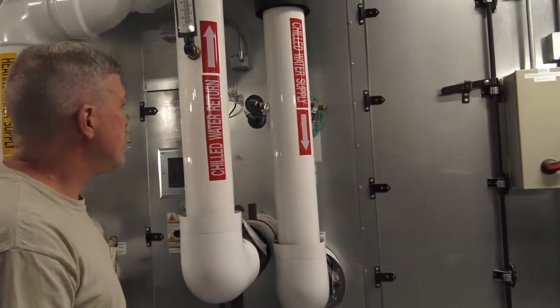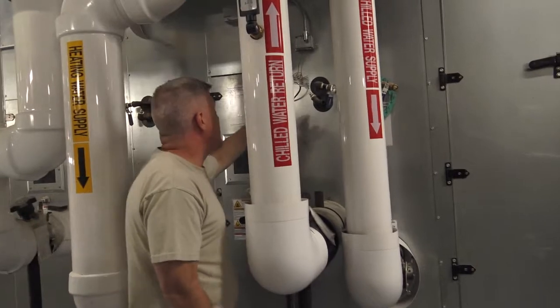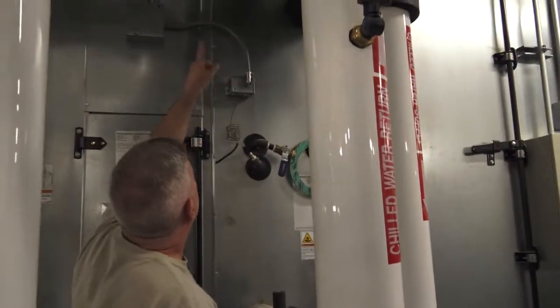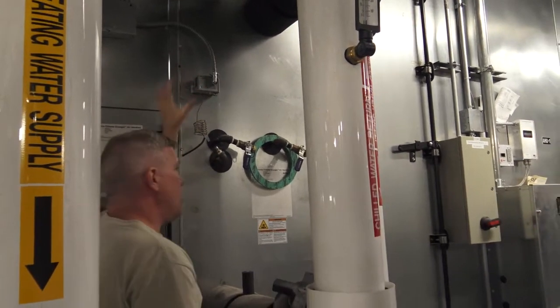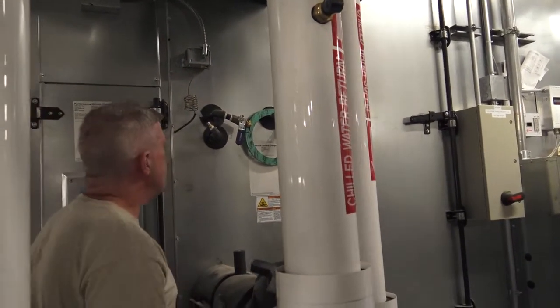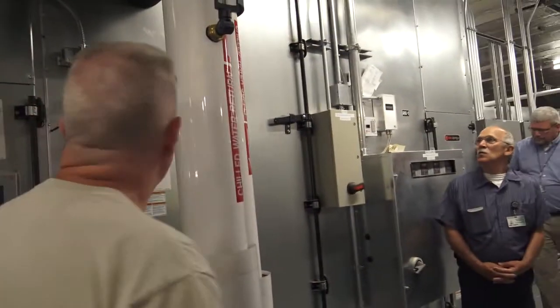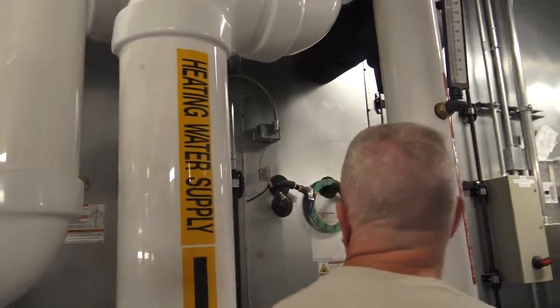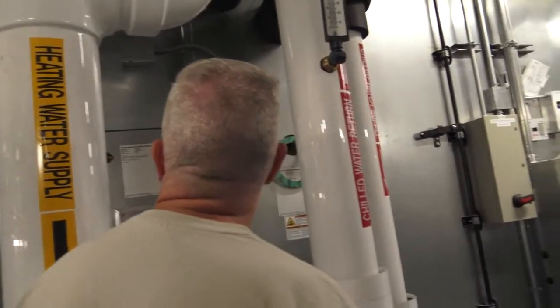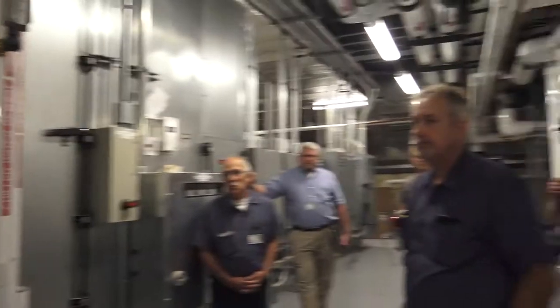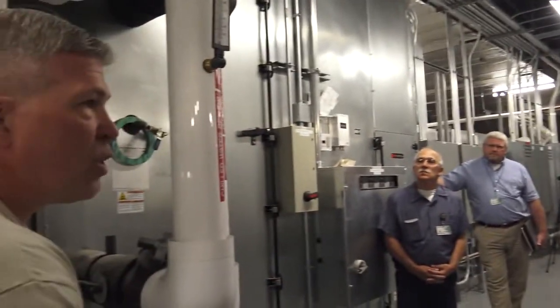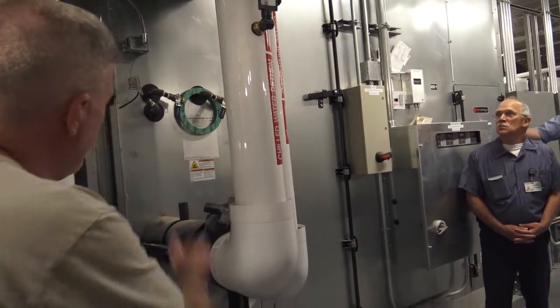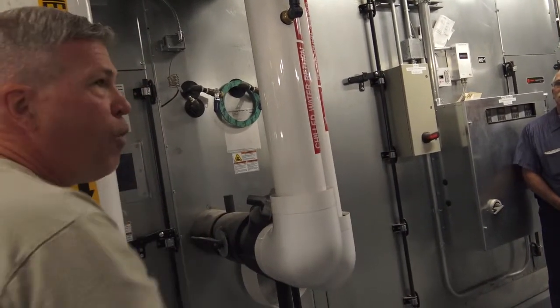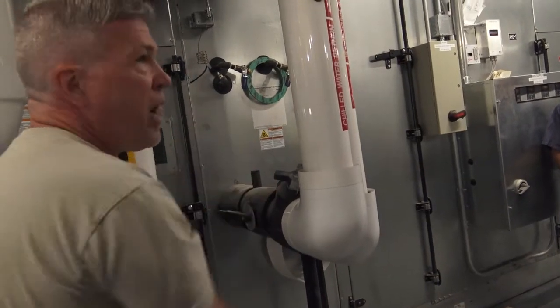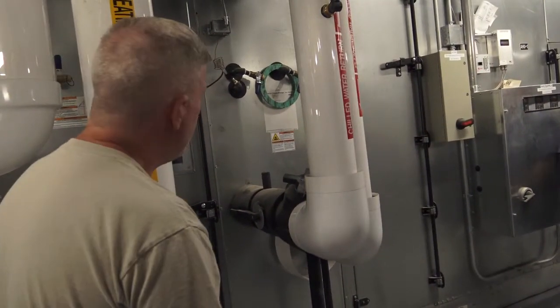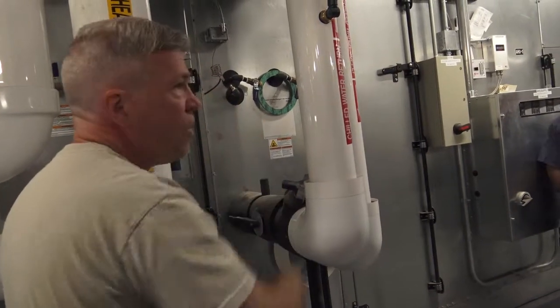So chill water section. This has 2 freeze stats on it. There's one here. There's another one way at the top. Each one of those just kind of covers one section of the coil. So again, when a freeze stat trips, that's when you want to reset it. You got a little door so you can get in that section at least. That's if the coils are getting too cold or clogged. It's mainly for during the winter. If we're bringing in outside air and it's like 0 and it gets too cold in here for some reason, say your hot water valve fails or something, below 35, those will just trip and shut the unit off, protecting the coil. Until someone hits the reset on there, it just won't run.